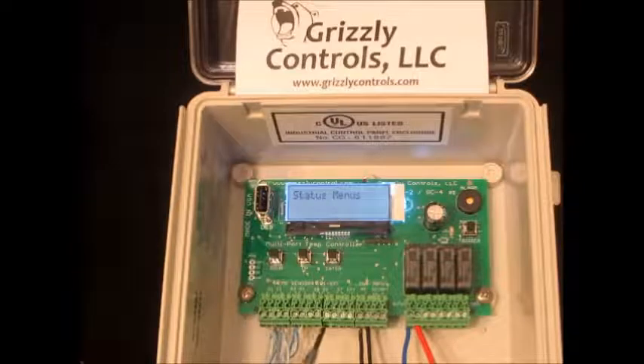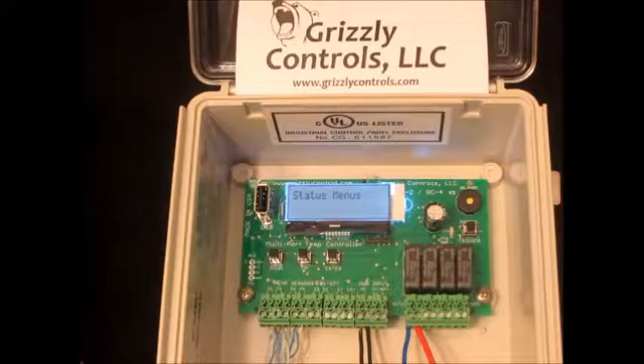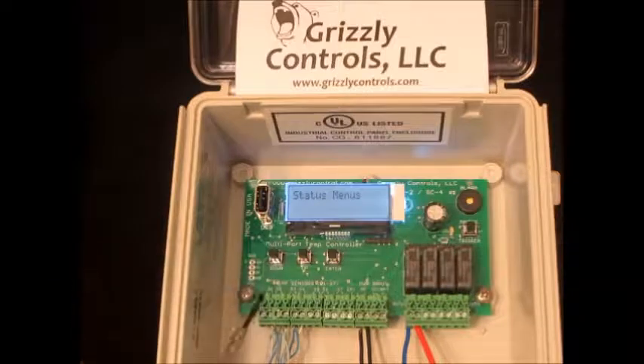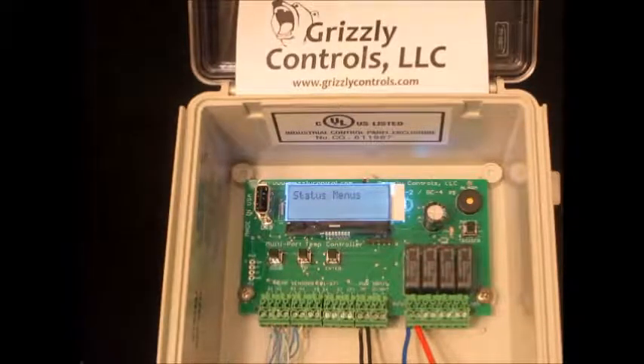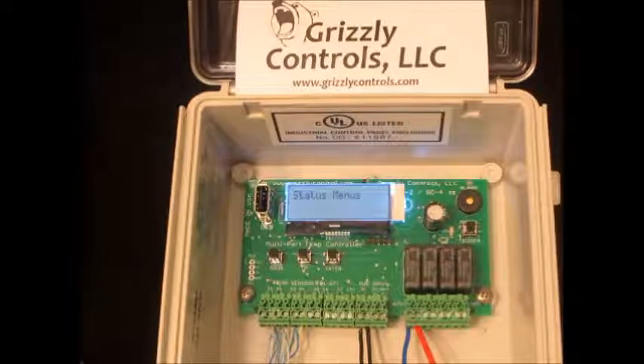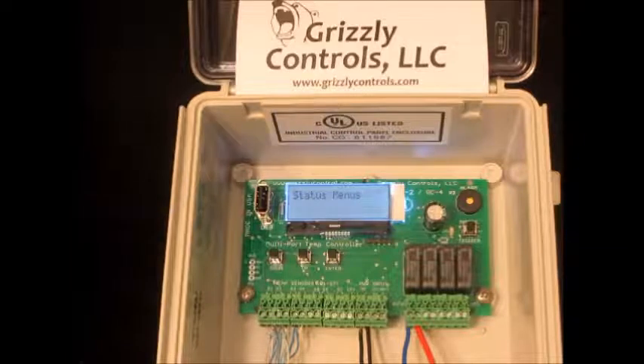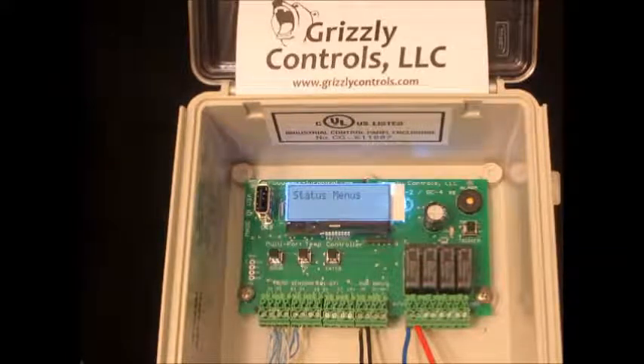Each of the inputs on the unit you can select for the different types. You can also configure them as a raw ADC input, for example, if you want to just read voltages. They also have individual calibration, so if you have an old sensor and it seems to be out of spec, it's not reading what you think the real temperature is, and you want to try to calibrate it, you can go into the controller on that input and put in a calibration setting to adjust it positive or minus based on your observed or measured temperatures.